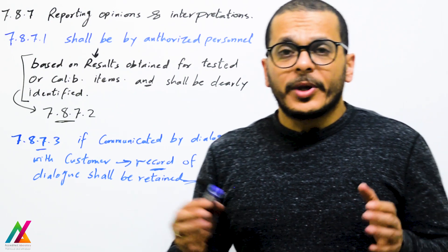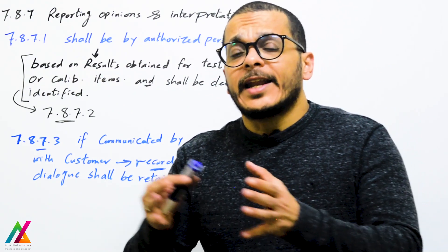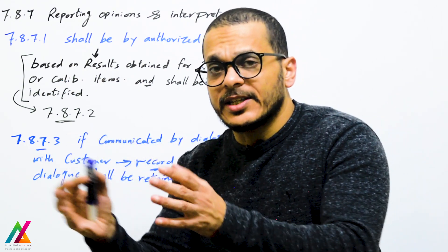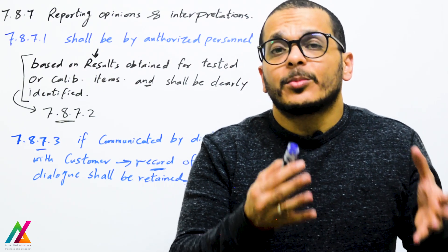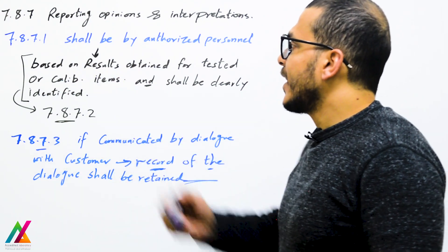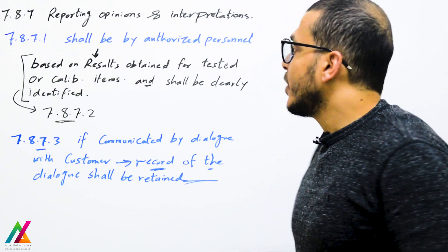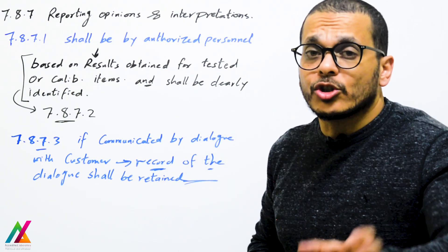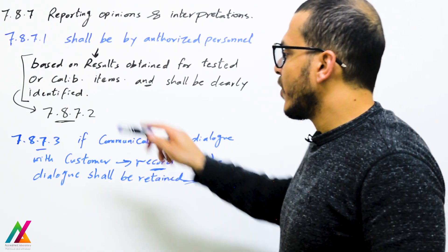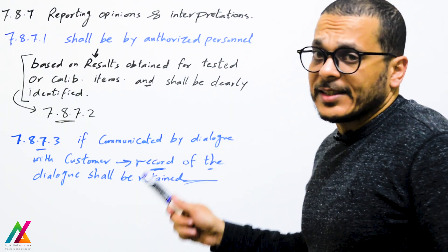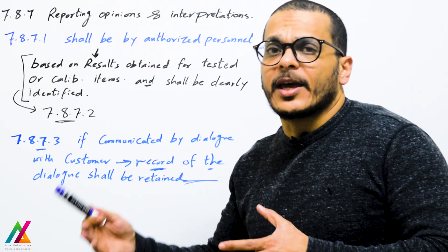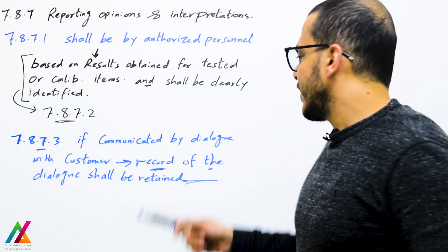Clause 7.8.7 covers opinions and interpretation. If the analyst has any information that will help decision-makers decide about a sample, or if there is any opinion or interpretation of the result that helps the customer understand the result, this should be included. Under 7.8.7.1, opinions and interpretation shall be made by an authorized person responsible for analysis of the sample based on results obtained, and shall be clearly identified. Under 7.8.7.2 and 7.8.7.3, if an opinion or interpretation is communicated by dialogue between the analyst or management and the customer, that dialogue shall be recorded and the record retained.